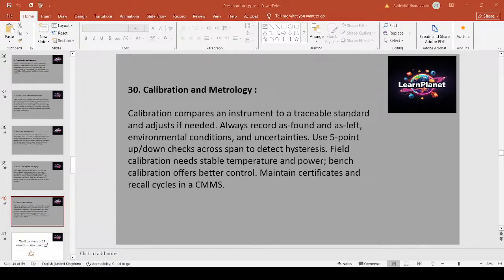Calibration compares instruments with traceable standards to quantify and adjust errors. Record as-found and as-left values, uncertainties, and environmental conditions. Use multi-point checks to detect hysteresis and non-linearity. Bench calibration is best for accuracy. Field calibration is practical but requires stable references. Track certificates and recall intervals in CMMS and include calibration acceptance criteria. Example: calibrate a flow transmitter using a calibrated flow prover and log as-found and as-left values into the CMMS.